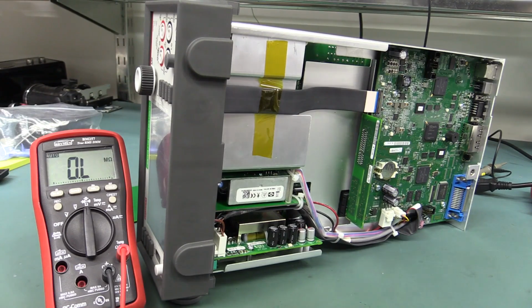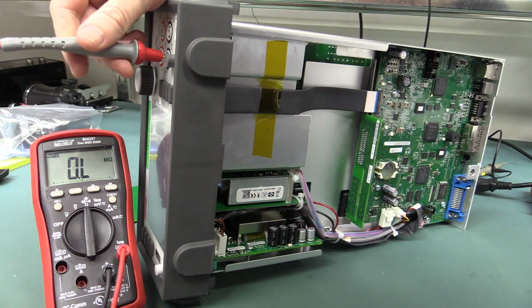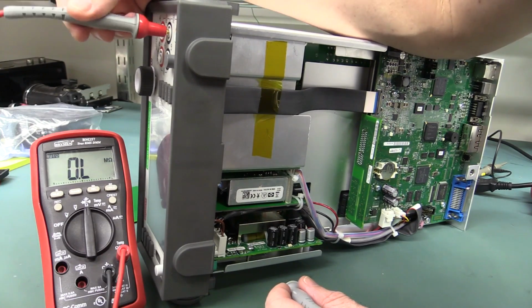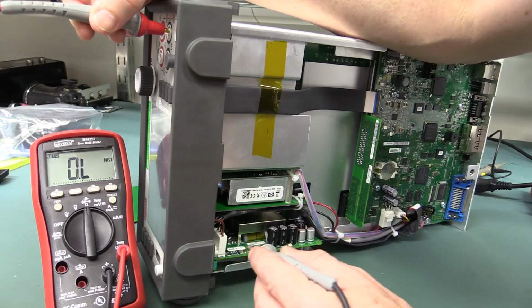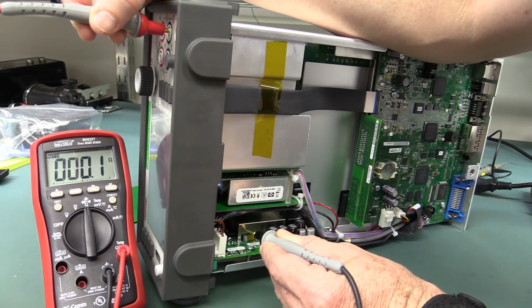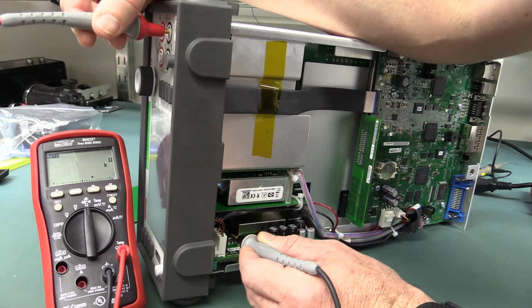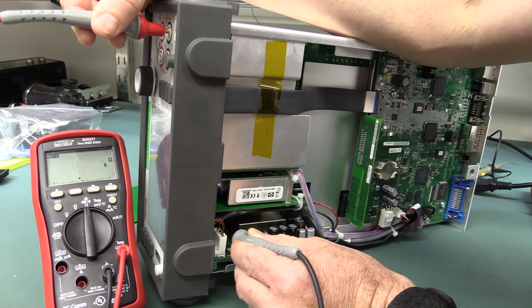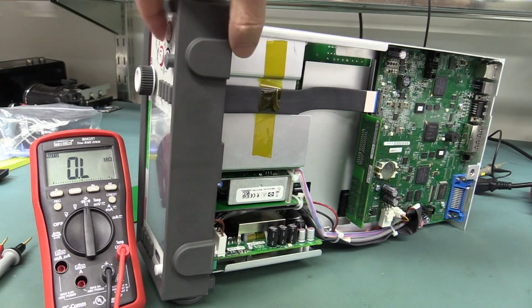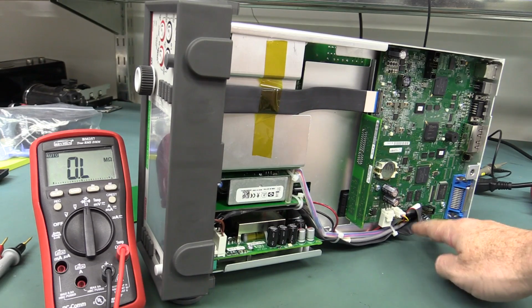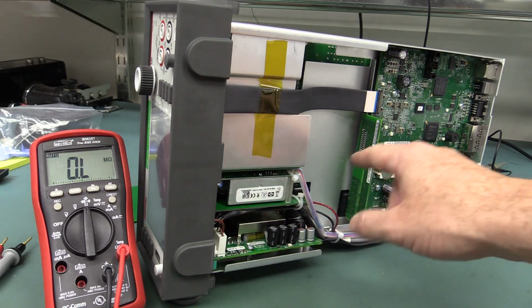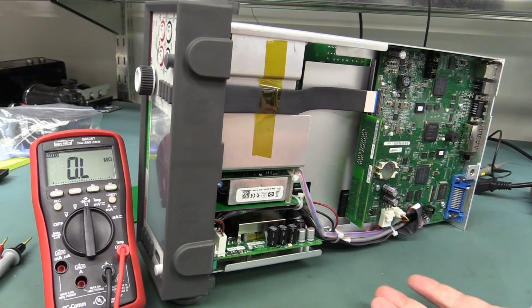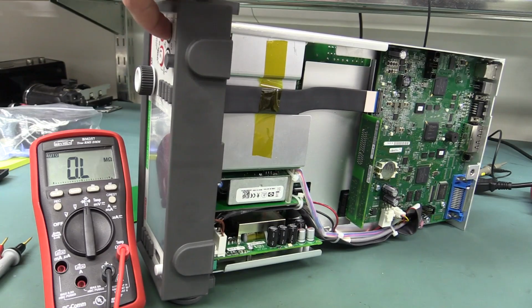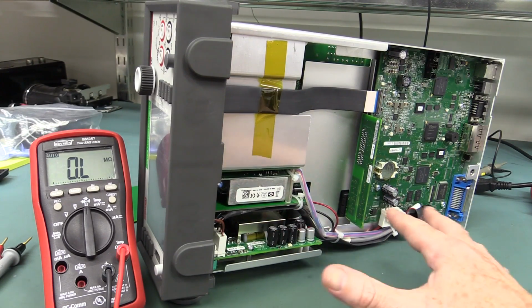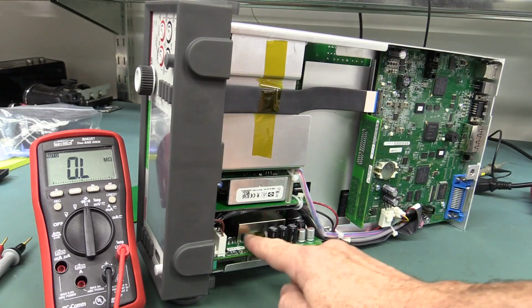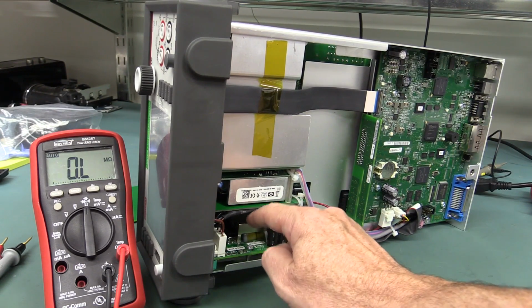You want to know where I reckon it's connected though? To our negative input. Bingo, look at that - it's connected to our input measurement ground. And of course that measurement ground is not mains ground earth referenced. They're doing that because in an analog measurement system like this, the negative input reference becomes everything, so it is not tied to mains earth reference.